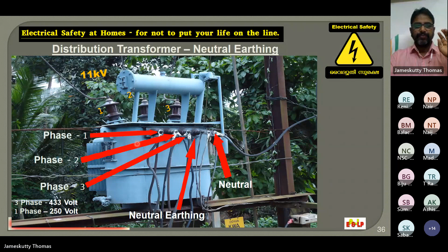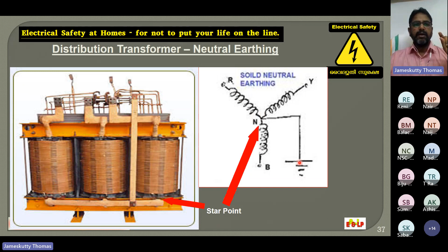See, here the transformer winding is shown. It is opened. The primary winding will be connected in delta, and the secondary winding will be connected in star, just like Y. It is the delta connection and it is the star connection. So the secondary side is connected in star. The midpoint of these connections, we call it the star point, because this connection is called star connection. That star point will be earthed, and that earthed star point is taken outward as the 4th wire, and it is called the neutral. Here in this diagram, you can see the neutral point, neutral and neutral earthing.